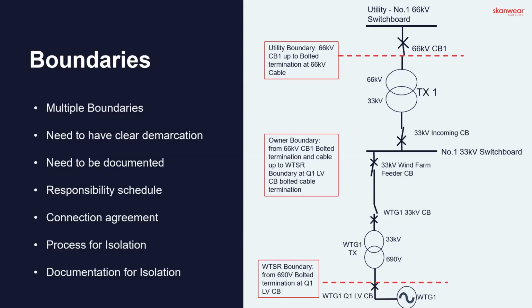So if I needed to work on that 66 kV to 33 kV TX1, I can't achieve isolation and achieve safety from the system myself because I have no control over that 66 kV circuit breaker one. This is where I would need to have those communication channels open, utilizing my responsibility schedule so I know who I need to contact and that it's outside of my area of responsibility, because I would need a cross-boundary isolation by the utilities in order to ensure that I've got safety achieved from the system to work on TX1.